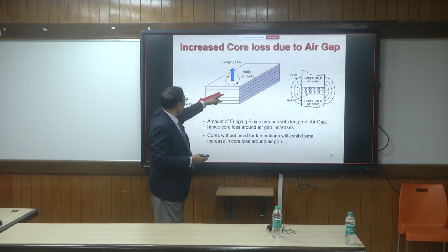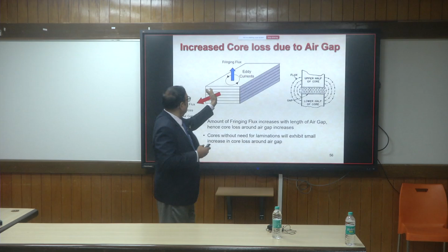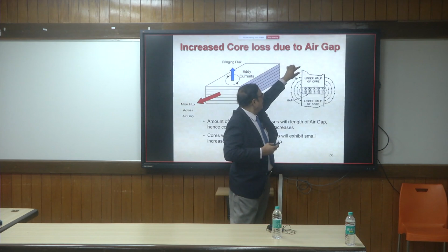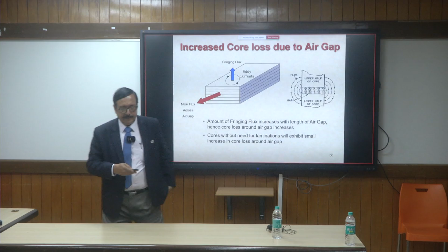It will not happen in ferrite cores. It will only happen in cores that are laminated to reduce eddy currents. It will happen in your CRGO type of cores. It will happen in your amorphous cores. So what is the way? You keep your winding away from the edge. Don't keep the winding close to the edge. Keep it away, then you will be safe. If your winding is up to the edge, the insulation will get damaged because of the high temperature.